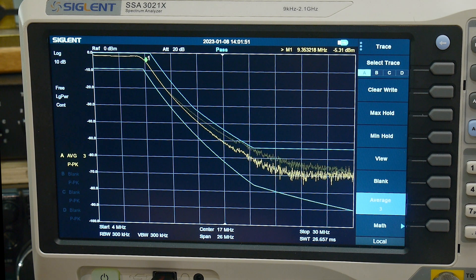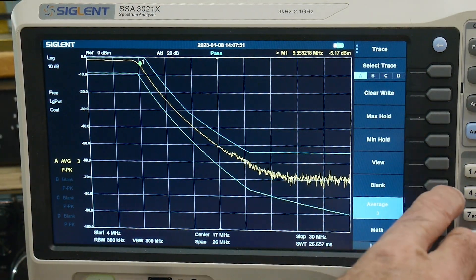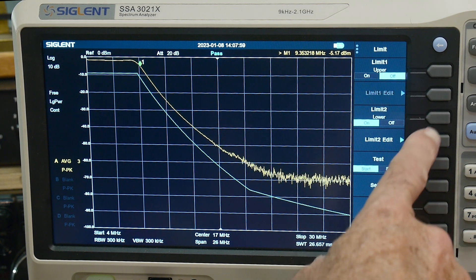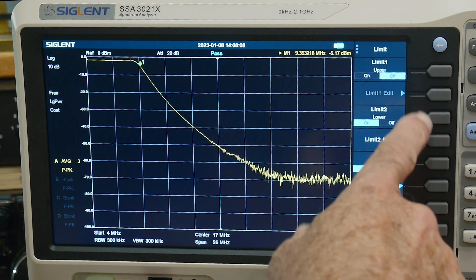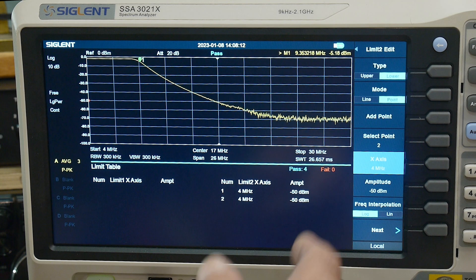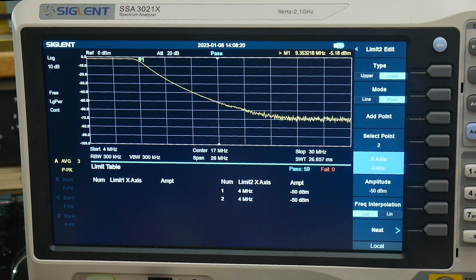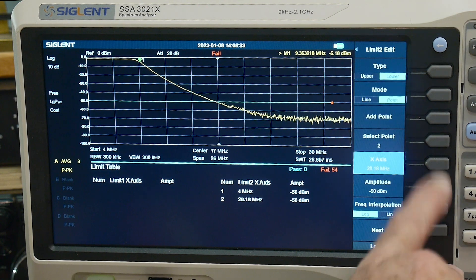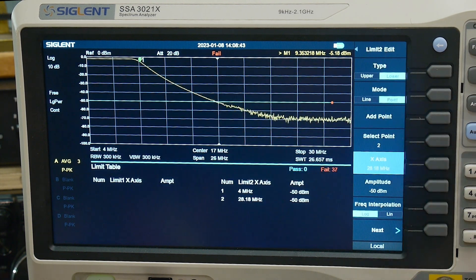Let me give you a quick example starting from scratch. When you go into limits, we'll turn the upper limit off, do just the lower limit, edit it, and delete all — so now you have nothing in there. We'll go back, edit limit two, and add a point. It beeps a lot because we're out of bounds, so let's go into setup and turn off the buzzer.